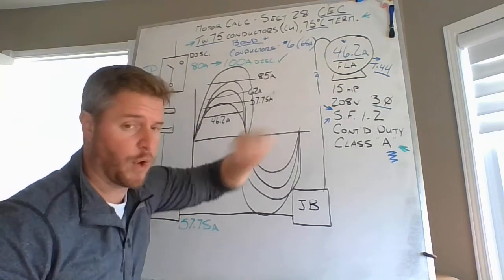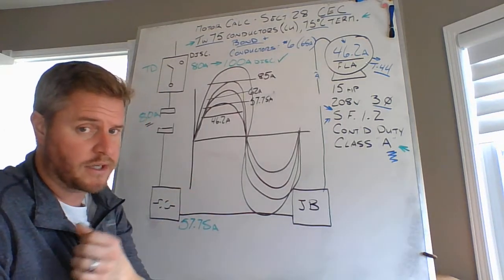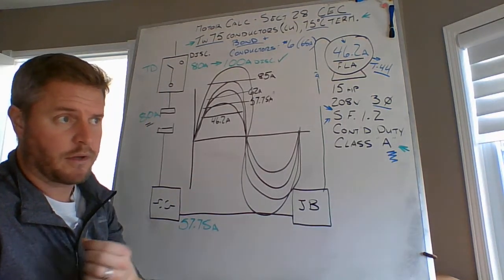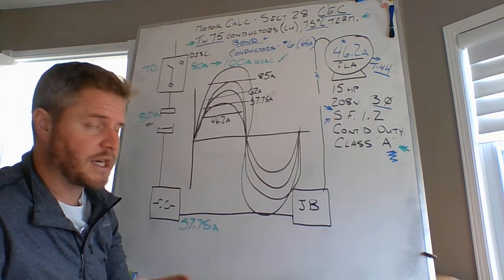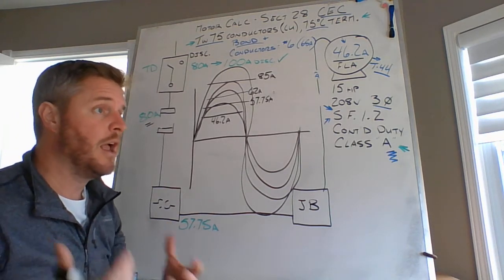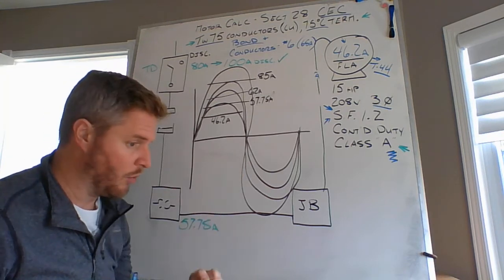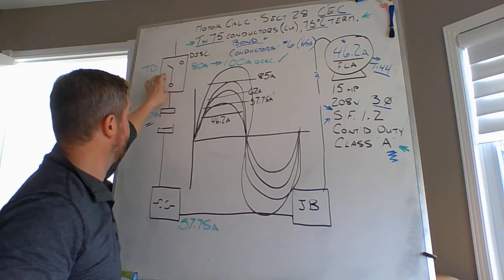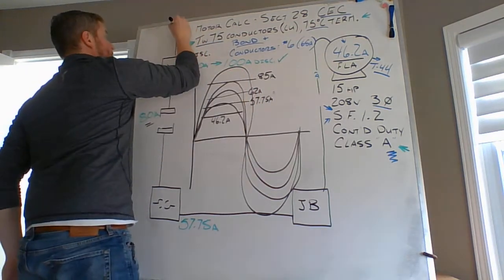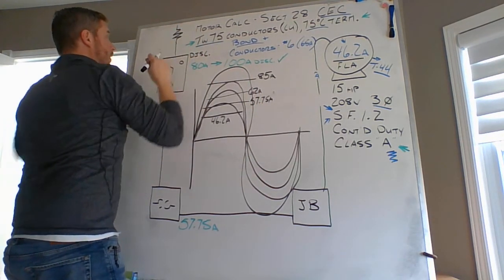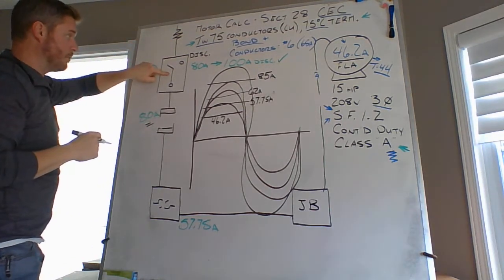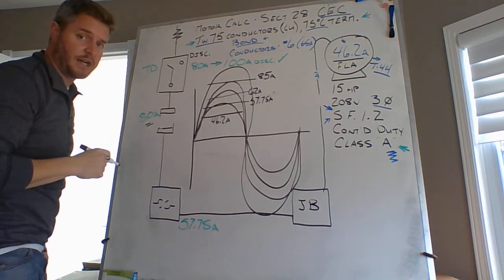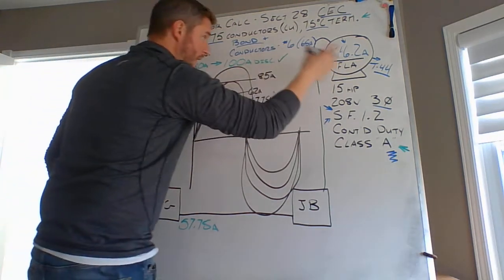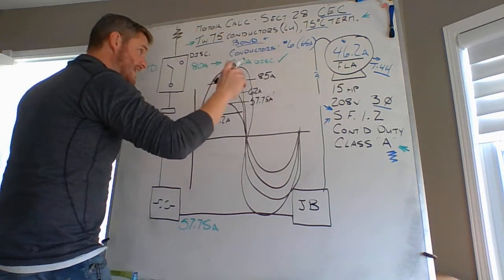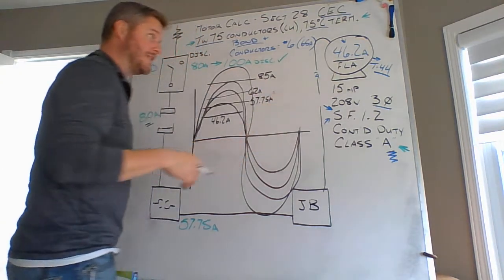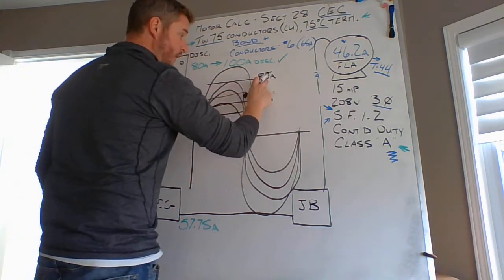And that shuts down everything. It's not a reset on a time delay fuse. You have to stop your operation. You have to disconnect everything. You have to go to your main motor control panel, shut down that disconnect so that you can replace these fuses. You have to shut down these conductors up here. You have to turn these ones off so that you can replace these 3 fuses inside that disconnect, because you overloaded that motor. That motor was never designed to carry more than 46.2 amps, and you forced it to do 85.